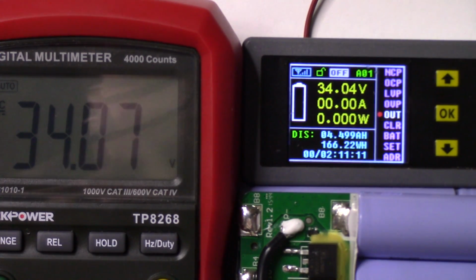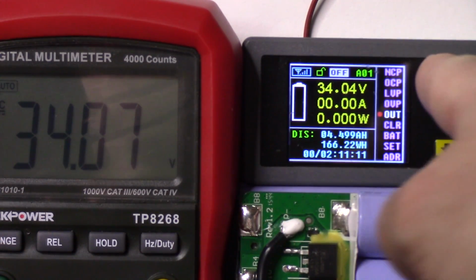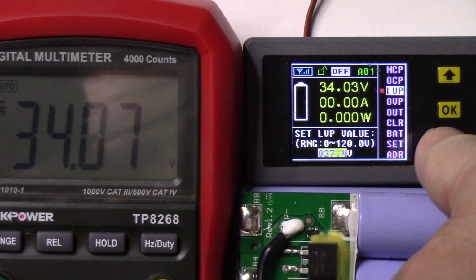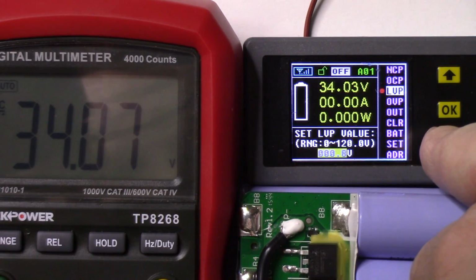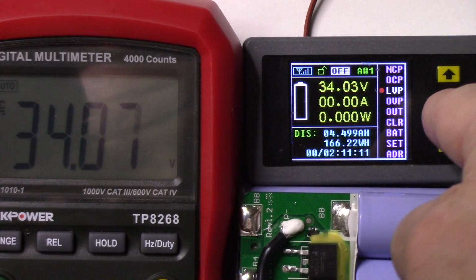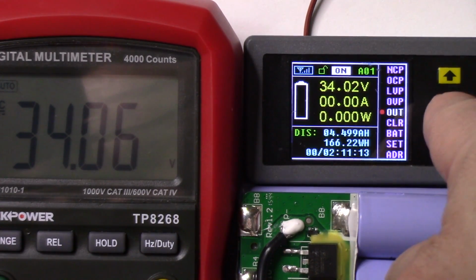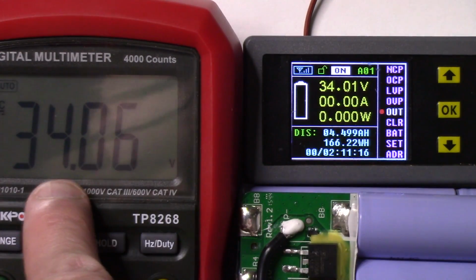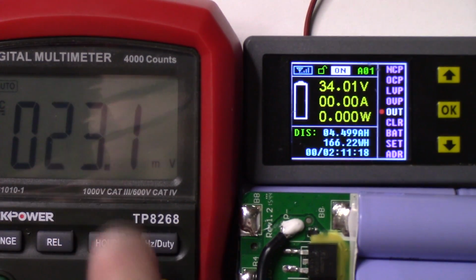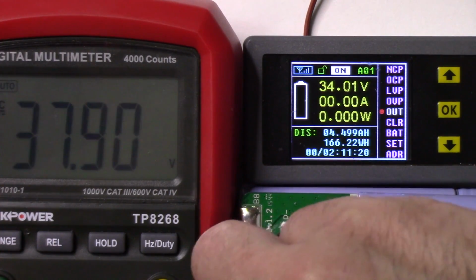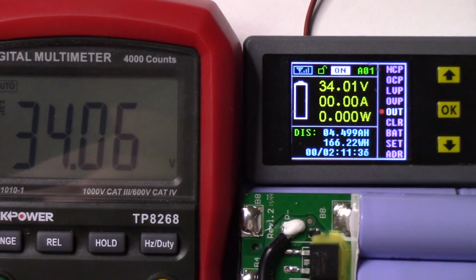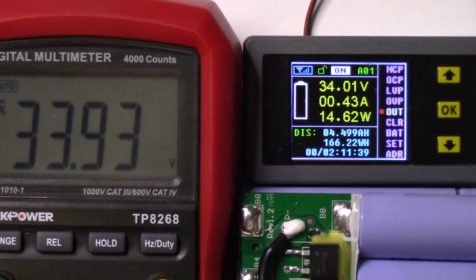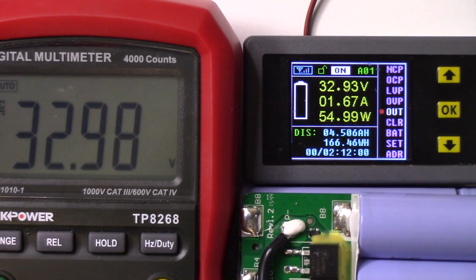So let's discharge this down past that — I'm going to turn the low voltage protection off, and basically what I'll do now is discharge it until it actually disconnects again, and show you that on video as well. Low voltage protection is off, and the circuit is on. The battery voltage currently, when I don't knock the lead off, is 34.06. Let's turn on my load here. All right, we're at 1.67 amps. I'm going to let it run down and see where it cuts off.